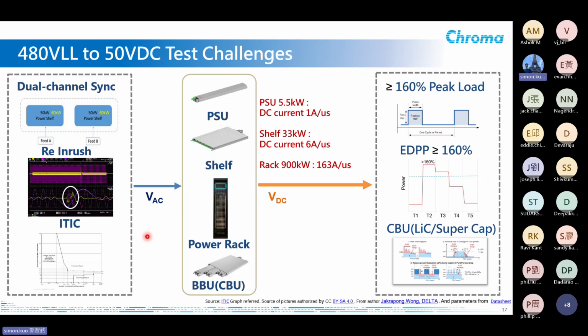And this is for the AC side. On the DC side, the peak load is stated clearly, as I already showed. The EDPP is actually required by the GPU testing, so this test is not defined in the specification of the ORV3 as well. Not only BBU, but capacitor backup units are also proposed recently because of the maximum peak load drawn by the CPU and GPUs. Okay, so we have the AC side testing challenges, we have the DC side testing challenges.